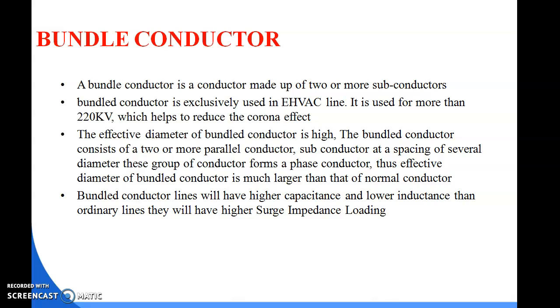Okay, clear? So a bundle conductor line will have higher capacitance and lower inductance than ordinary lines. They will have a higher surge impedance loading, called SIL, with bundle conductors.